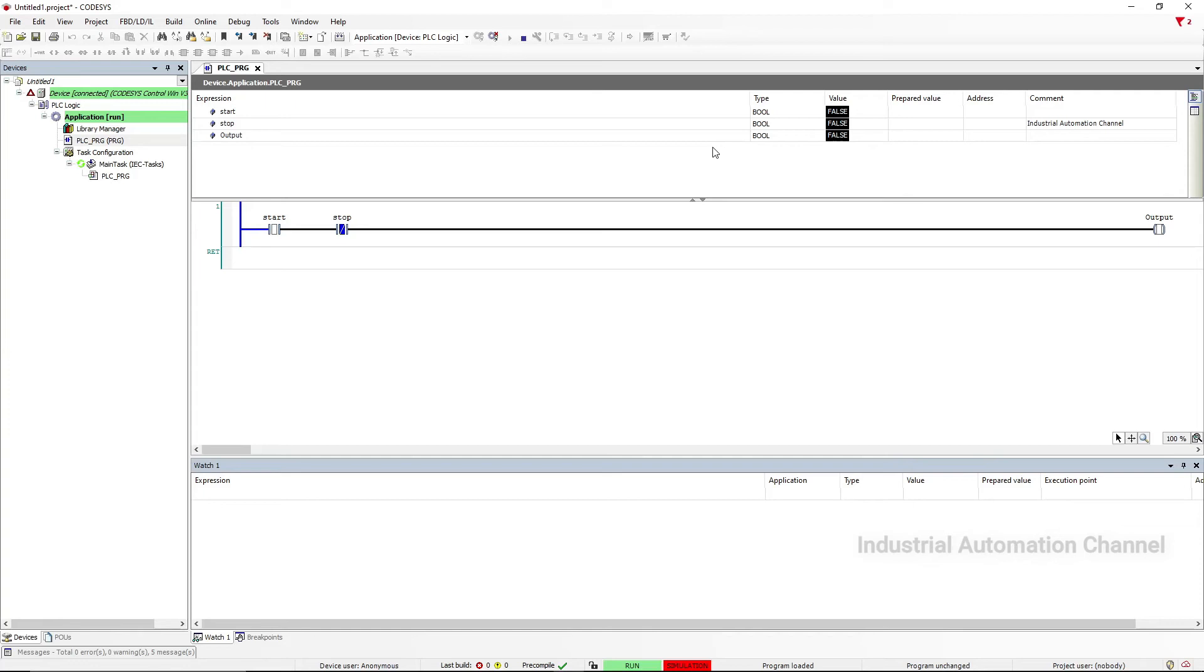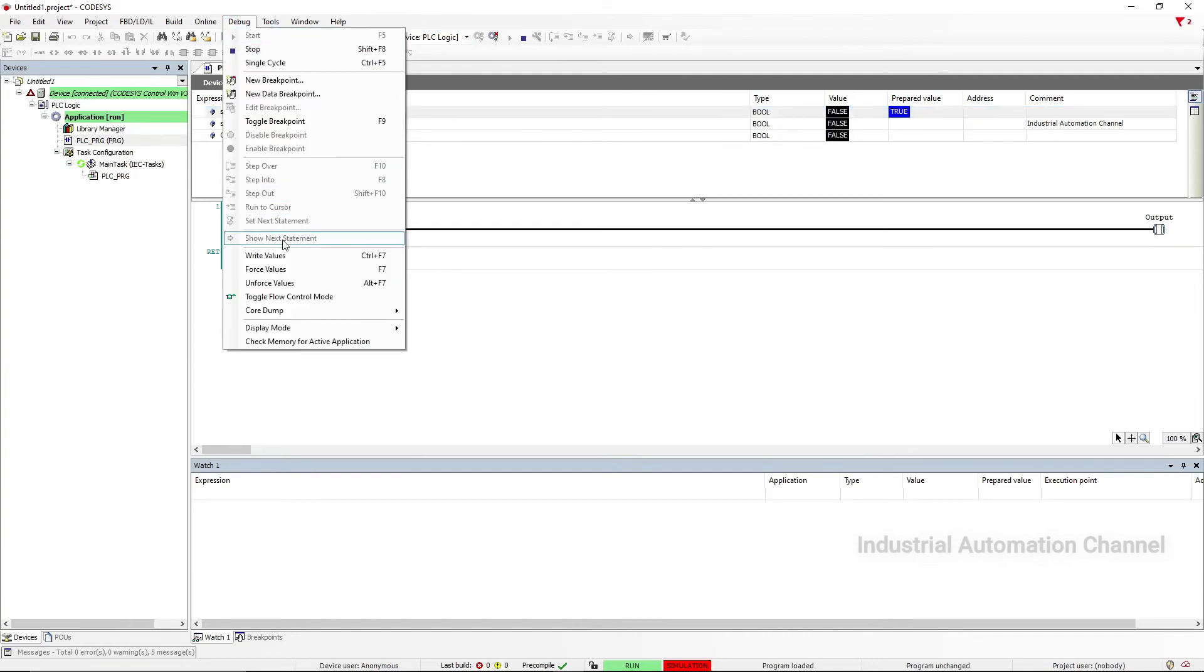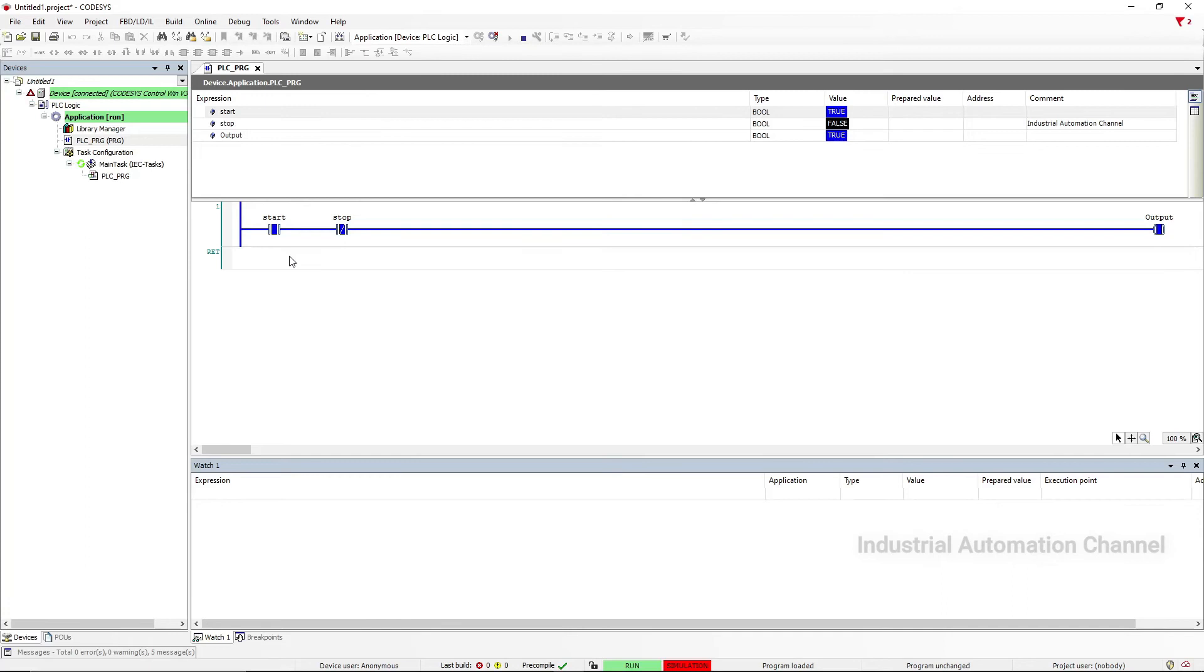We can see a list of relationships between variables and expressions here. We can change or write and force the value of our variables. Click here. Each time you click you will see the available values that we can use. We can set it to True, False, or don't change. For example, I want to change the Start to True. Select True and then from Debug select Write or press F7 on your keyboard. You see Start is now activated, or we can say it has a logic True. Whenever the value for a Boolean variable is True, it's highlighted with blue, and whenever it is False there is no highlighting.